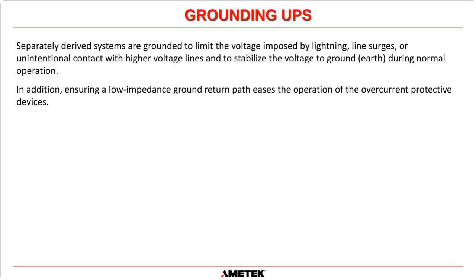And separately derived systems are grounded to limit the voltage imposed by line surges or unintentional contact with higher voltage lines, and to also stabilize the voltage to ground or earth during normal operation. And in addition, it ensures a low impedance ground return path that aids the overcurrent protective devices to activate very, very quickly. It gives a nice easy path for any fault current to get back to the overcurrent protective device, whether that's a breaker or whatever it is in your MCC.